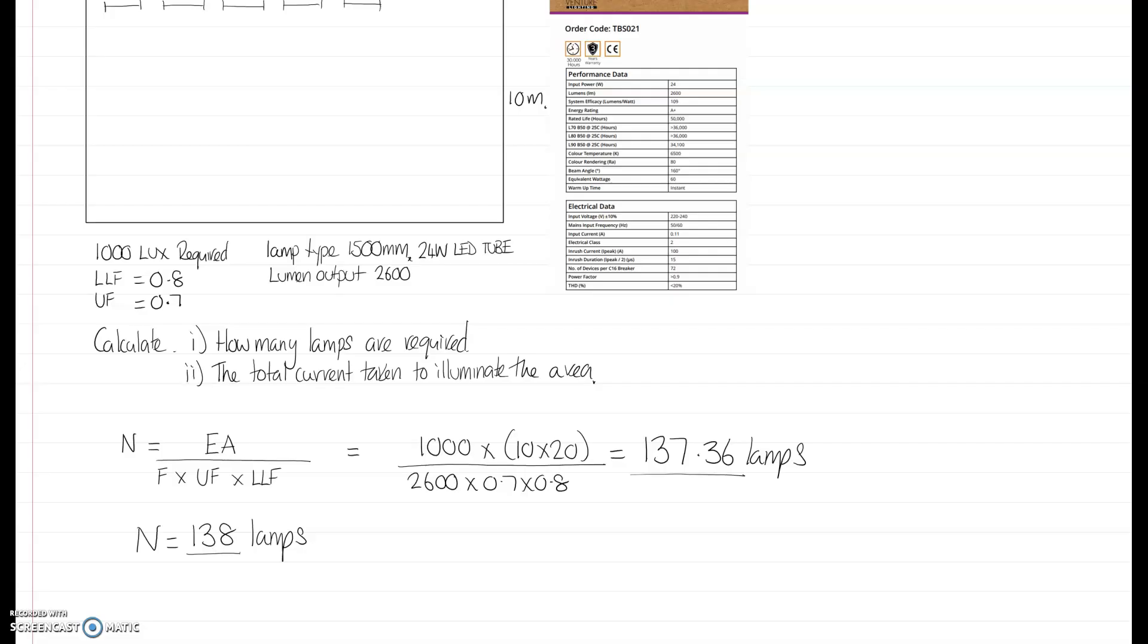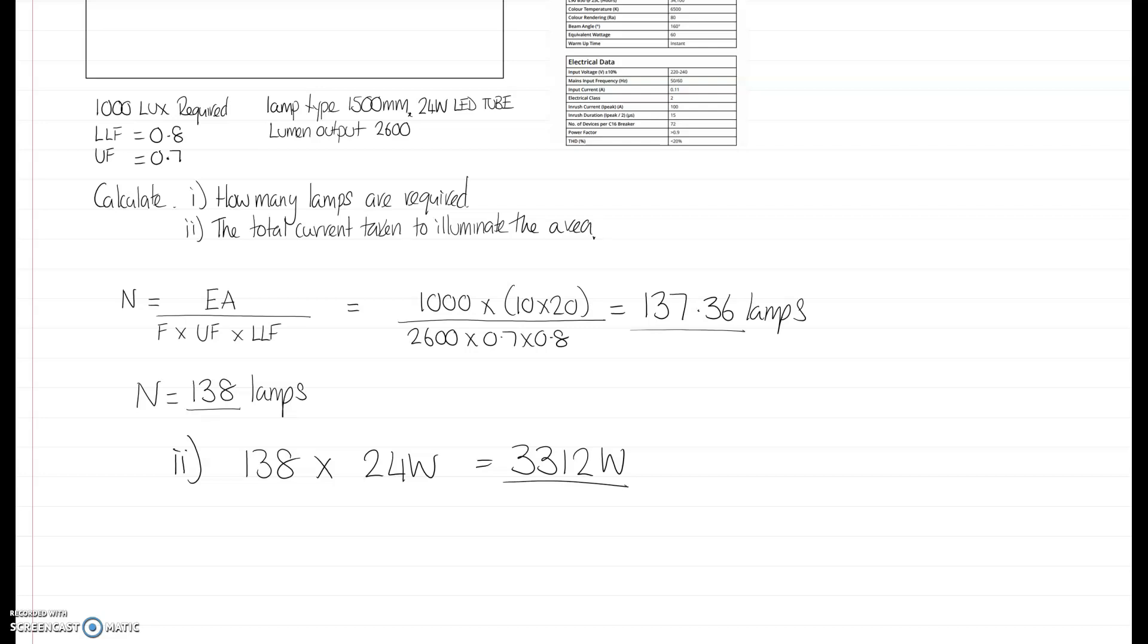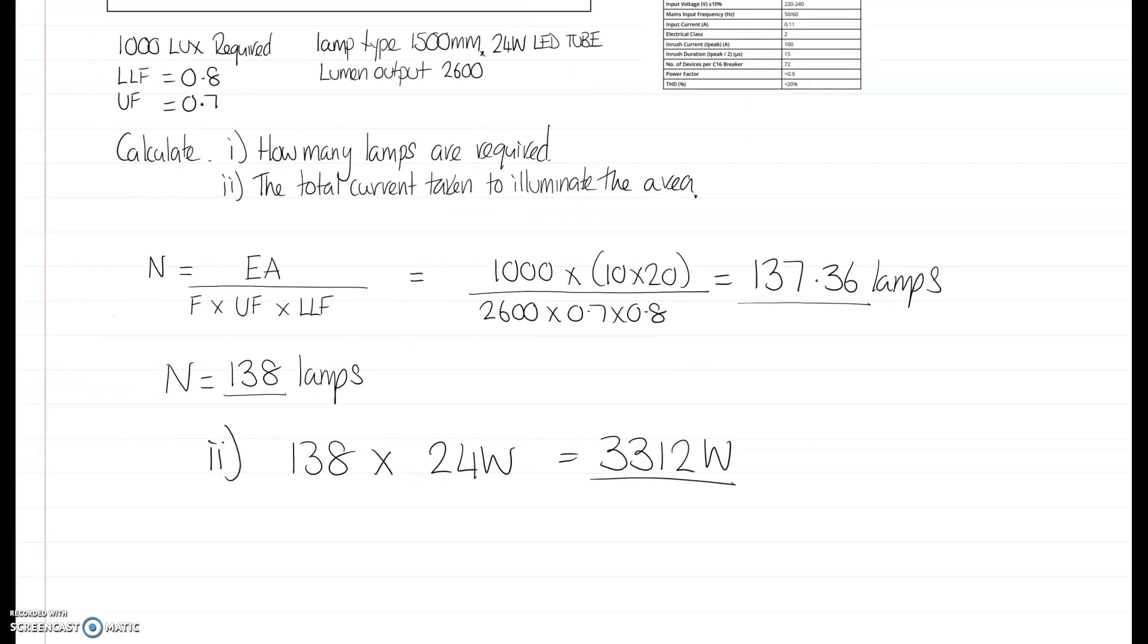How much current is that going to take then? Well, if there's 138 lamps, so we've got 138 lamps times the input power which is 24 watts. So we get a total power of 3.31 kilowatts, which is quite a bit. But obviously we do that over three phases, but we'll stay with one phase for now.